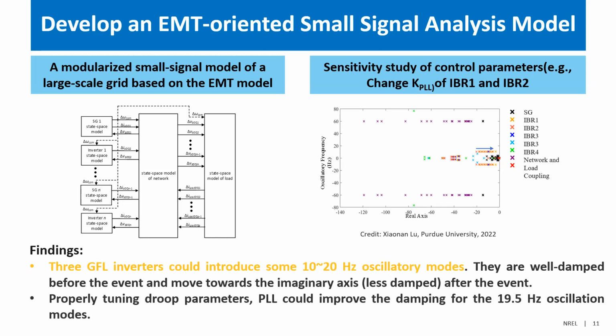We could easily find that these three grid-following inverters introduce these modes, and they are potentially the oscillation source responsible for this oscillation. Second, by analyzing the participation factors, we could pinpoint that the PLL and the current control loop play an important role in those oscillatory modes.